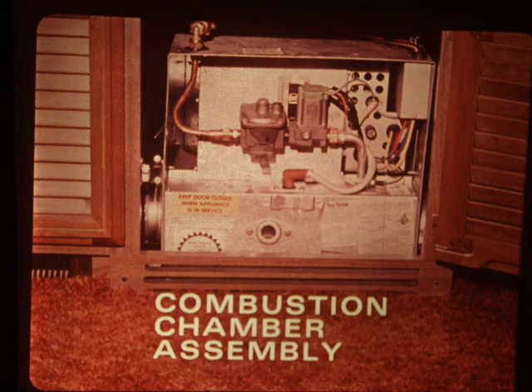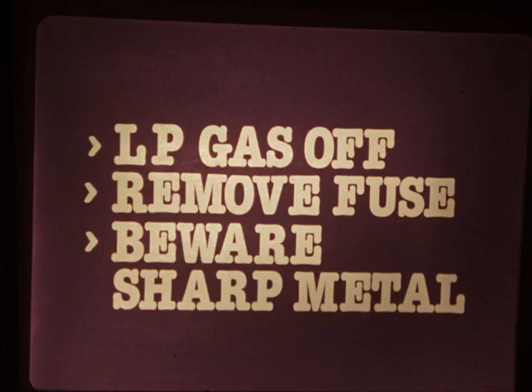To replace other components, you'll have to remove the combustion chamber. Prior to removing any component, be certain the LP gas supply is shut off at the supply tank and you've removed the furnace fuse. Also, beware of sharp sheet metal whenever you're servicing the furnace.